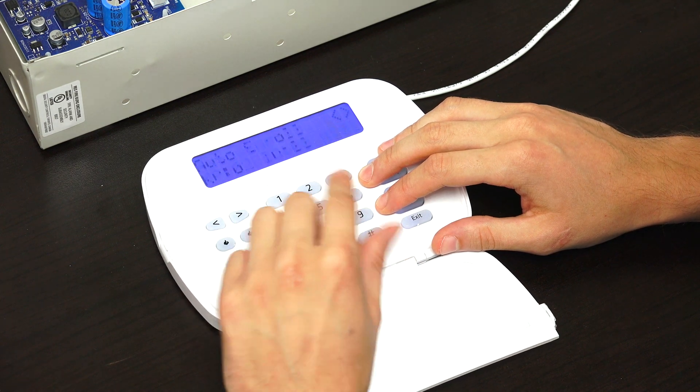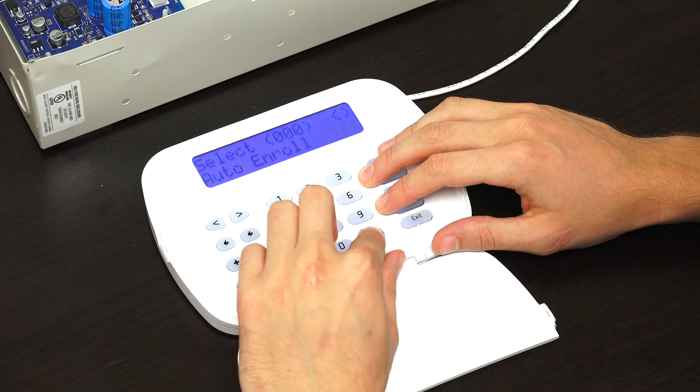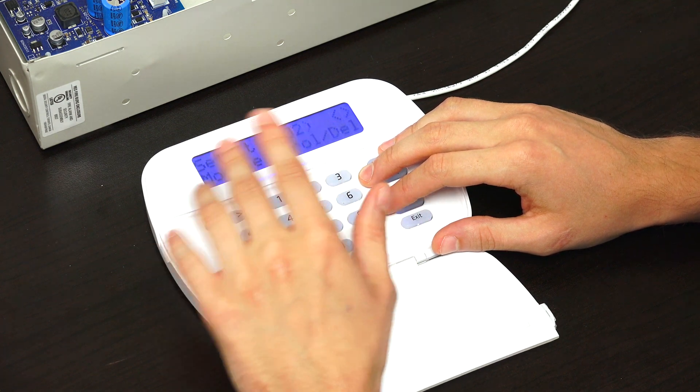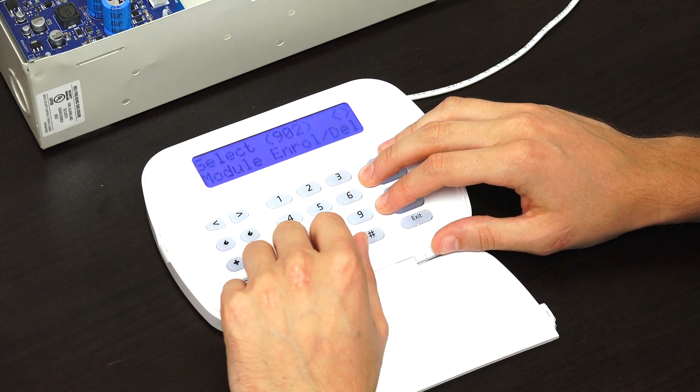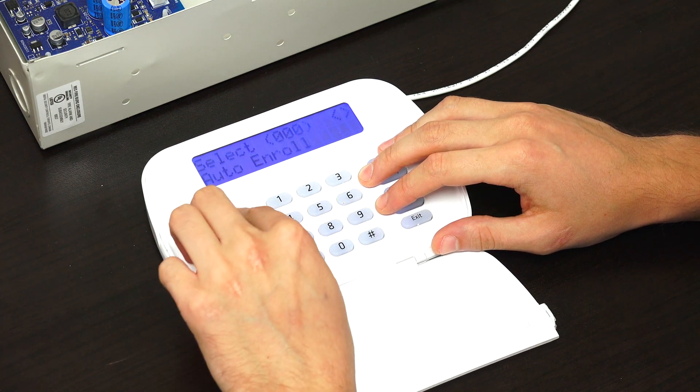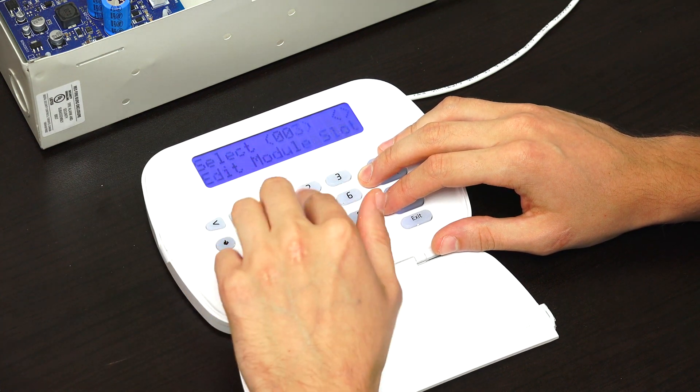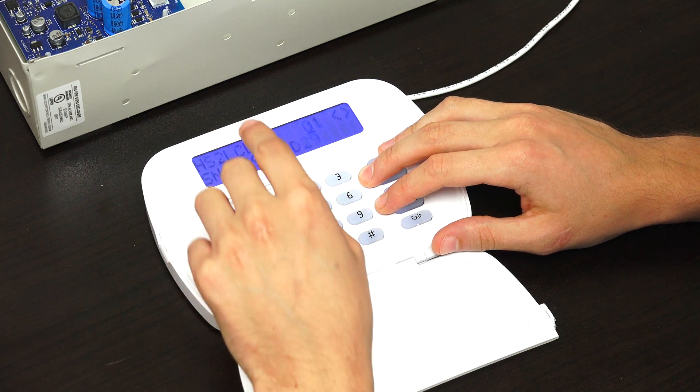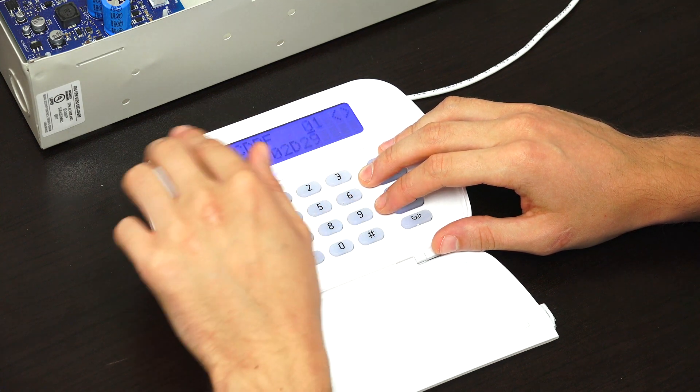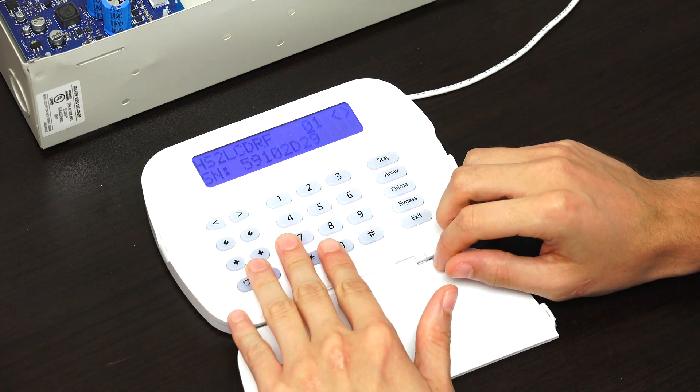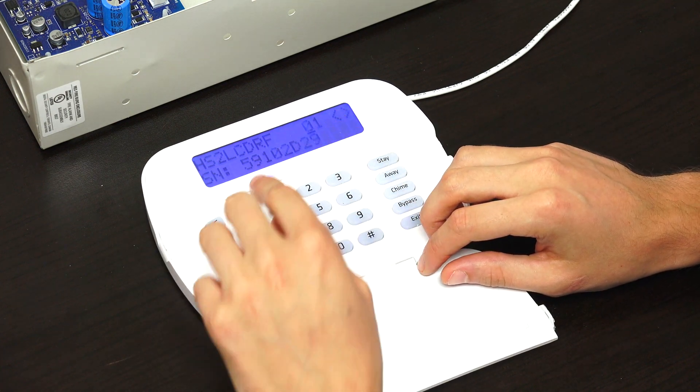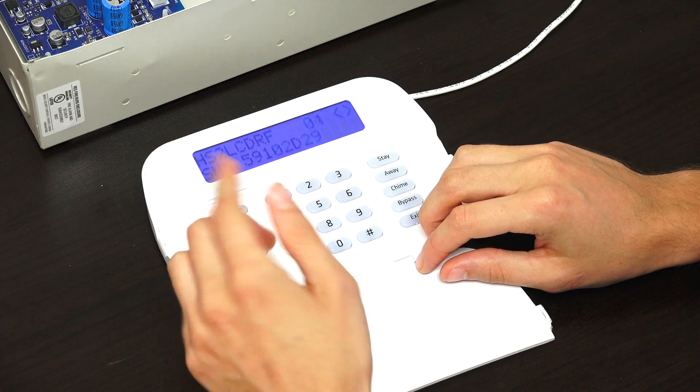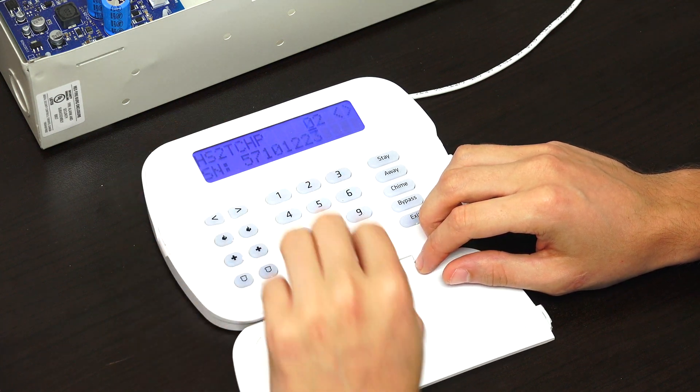If you wanted to manually assign it, you would access the 902 programming field. We're in 902, and we can select it. Then we'd scroll to 003 for edit module slot. Press star to confirm. We have our keypad here, the HS2 LCD RF keypad, and it is assigned to 01. If we wanted to assign it to 04, for instance, we could do so.